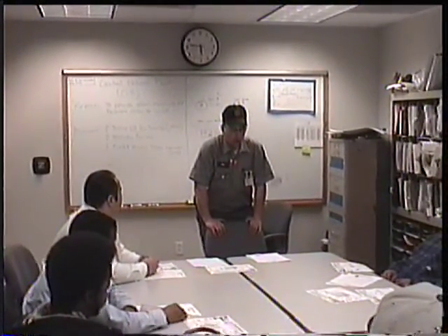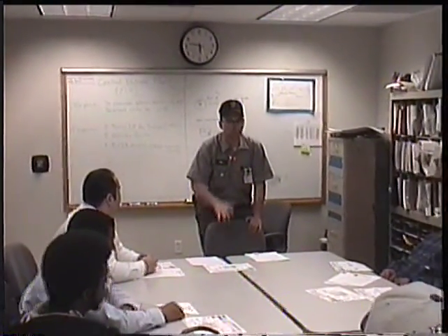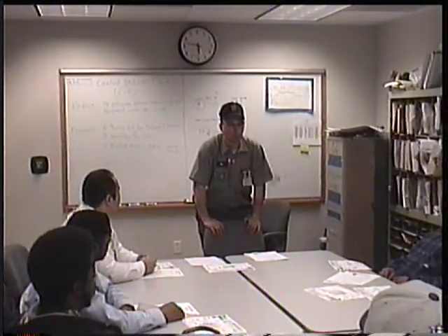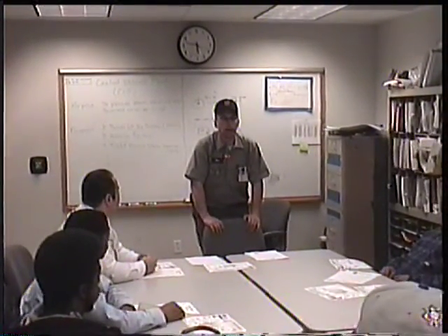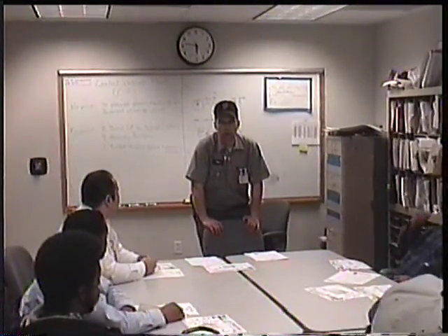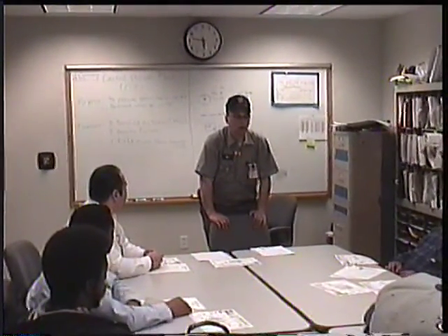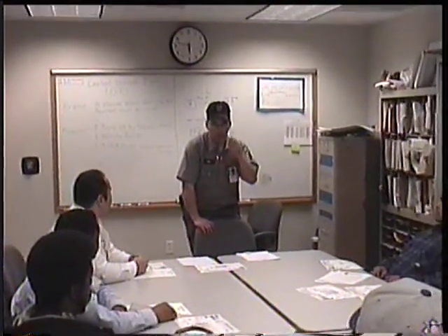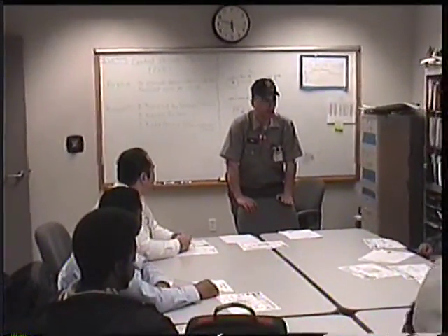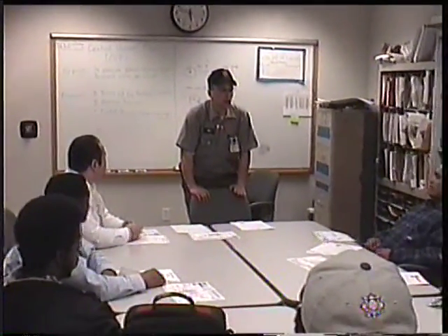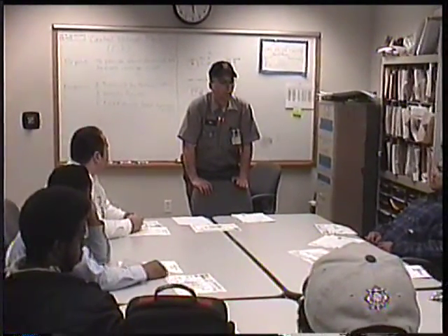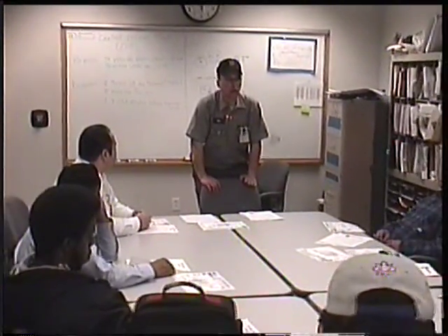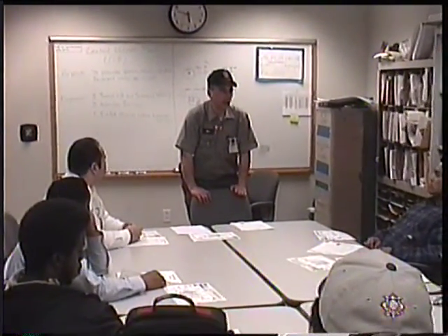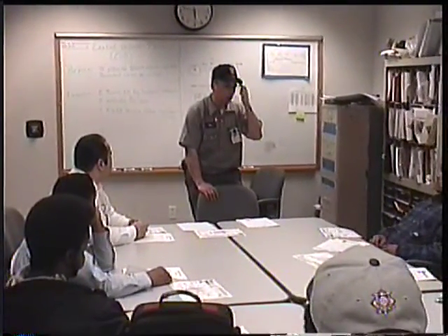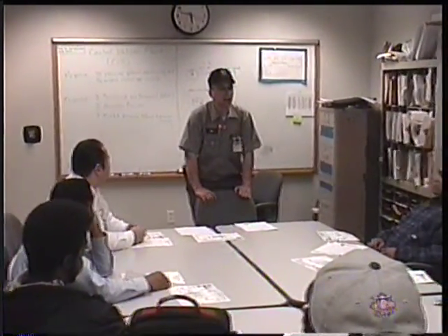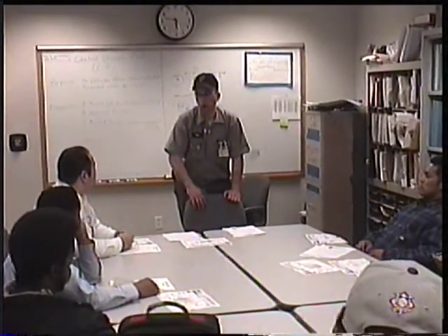The auxiliary boilers that we're going to be looking at tonight, we've actually had pretty uneven performance from. Number 1 boiler, which is the one we're looking at tonight for the most part, is down more than it's actually working. We've had burst tubes, cracked tubes, the superheater has leaked. I mean, pretty much everything can go wrong with the darn thing. One reason is that when they put in the chemical injection lines, they put them in the wrong areas. That was a design failure. We rectified that problem, but the damage was done during startup. That's how fast it goes. Startup was 6 months, from when they finished the plant.